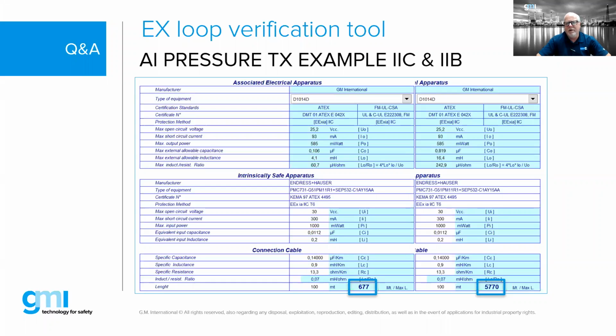It's important to understand the gas group when doing our calculations, because the cable length will play a major factor. For many applications, people don't have a huge issue with this since the control panel may be located within 50 or 100 meters of the end device. But in a big refinery or processing plant, this can be a very limiting factor, so we have to take that into account.